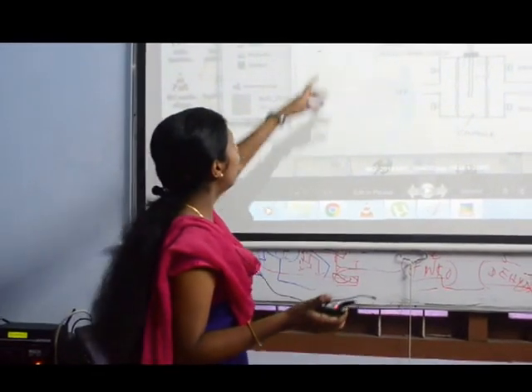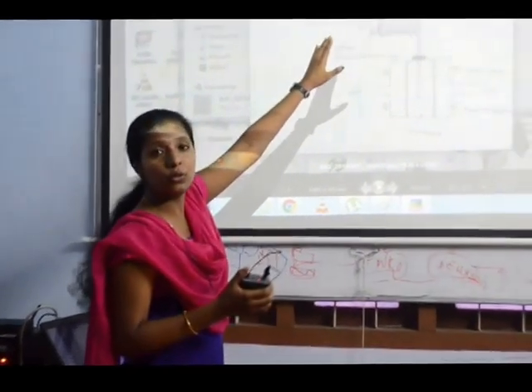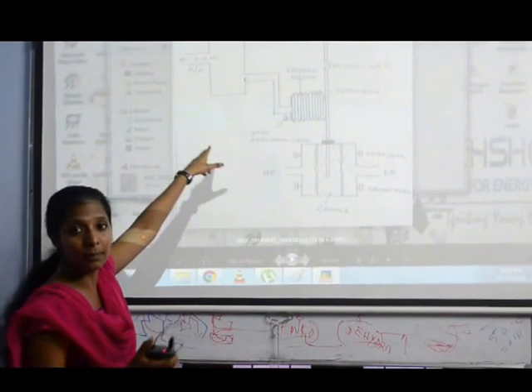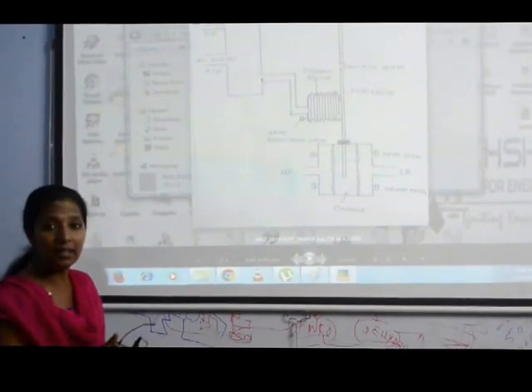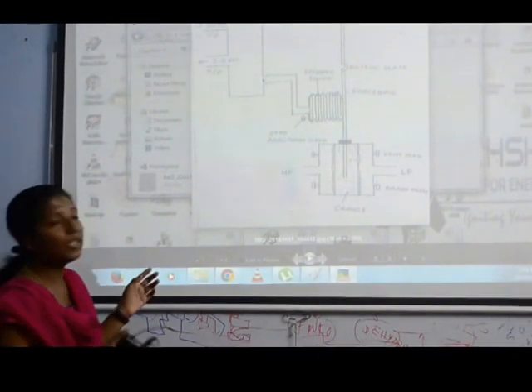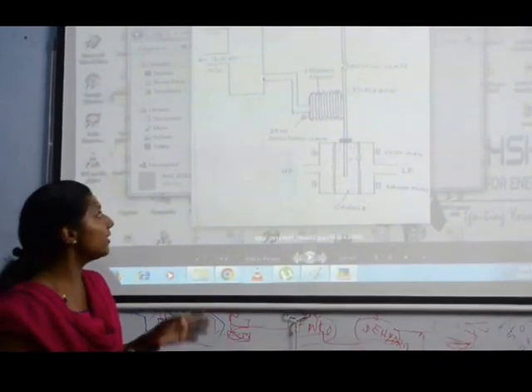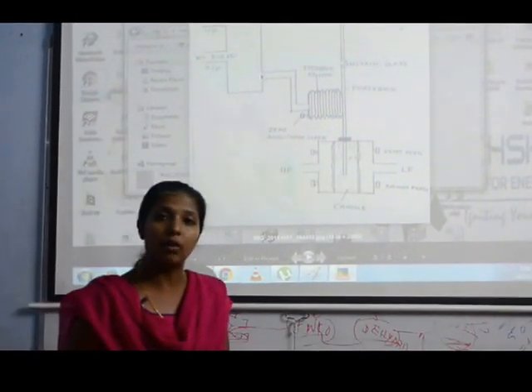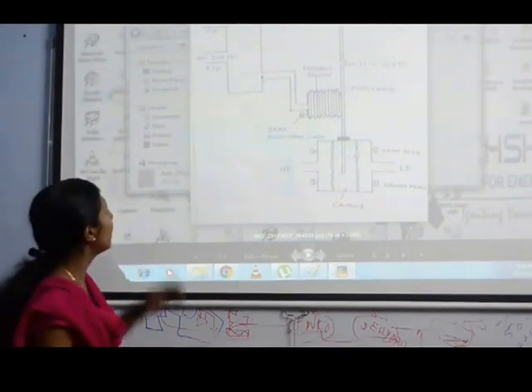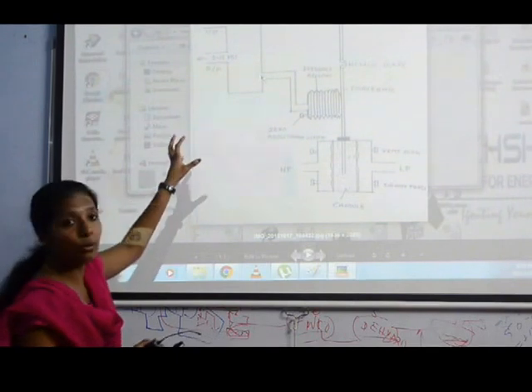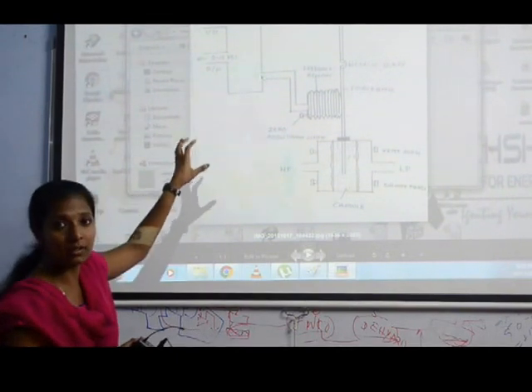The flapper nozzle is connected to an air supply or air relay circuit. Inside this air relay circuit, we are giving a 20 psi supply. That is the working supply of a pneumatic transmitter. That 20 psi is given to the air relay.